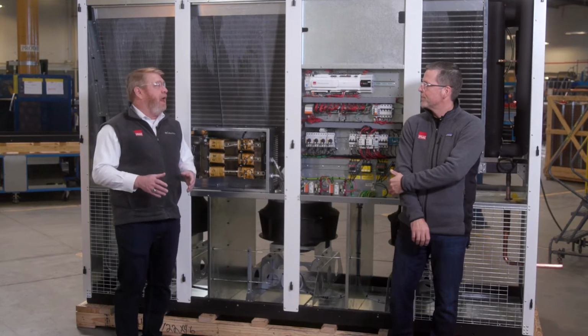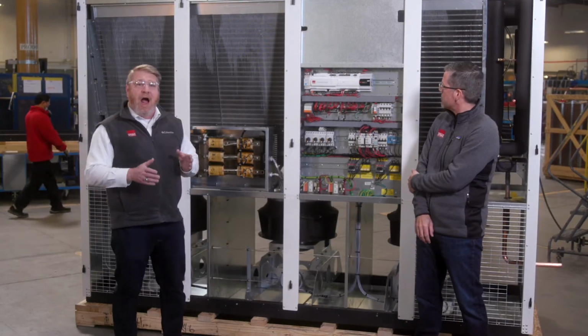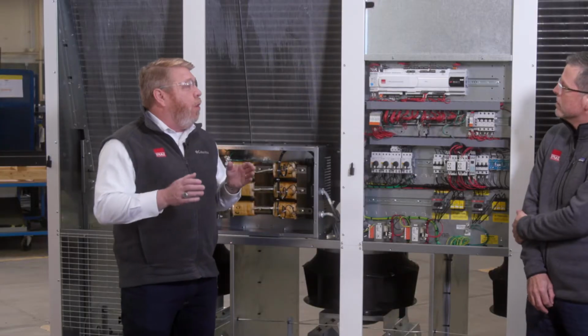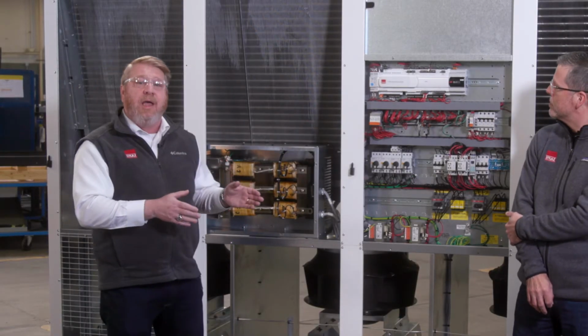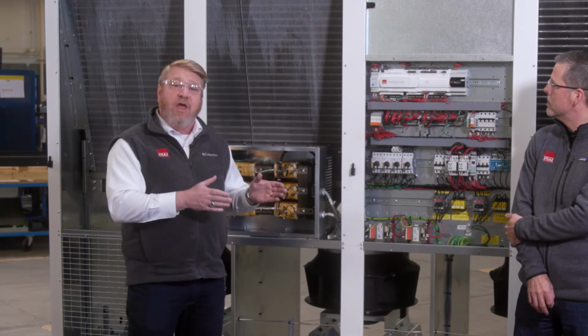So the last thing I'd like to point out is chilled water systems are highly customizable. When we go into a new facility, typically the engineer wants us to hit certain temperature differences across the coil on both the air side and the water side. So the vast majority of the standard equipment has several coils that can be utilized to hit these temperature differences. If perchance we don't have that particular coil, please contact the application engineering group. They'll be able to design a new coil if necessary and provide you with those performance metrics that you have to hit.